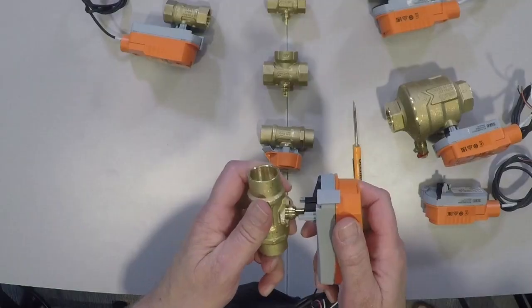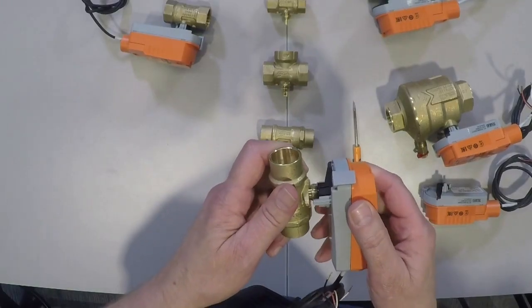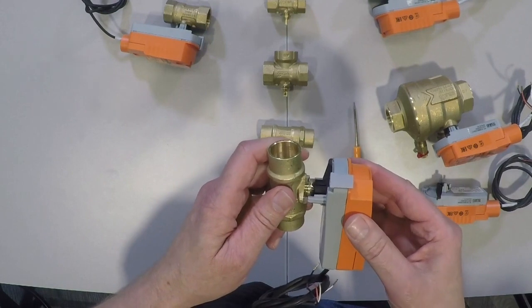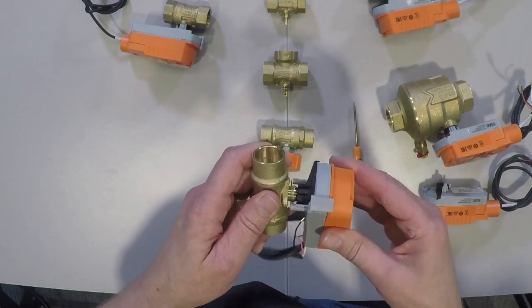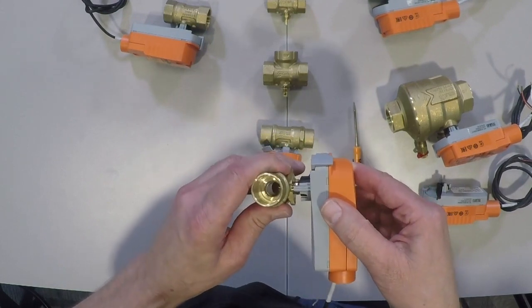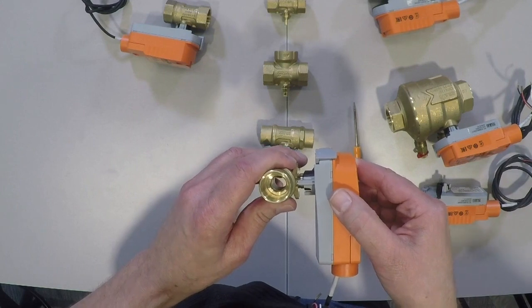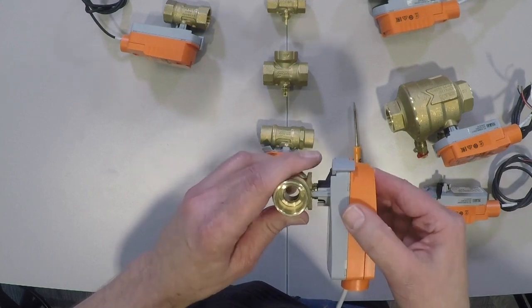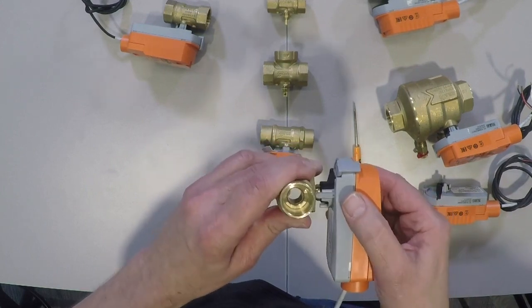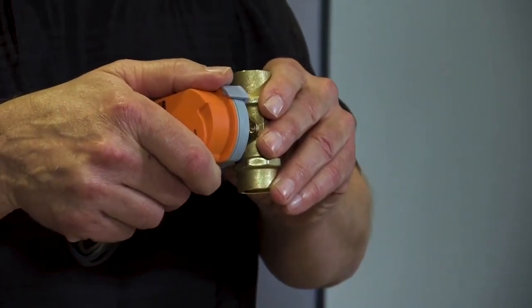If you come to the job site and you don't want to use a screwdriver or a wrench, what you can do is go to place the actuator on. It won't go. Very gently, hold a small amount of pressure up against the valve body and the stem, and begin to rotate the actuator very gently. When the actuator is lined up with the shaft, it's just going to move a tiny bit, maybe an eighth of an inch.